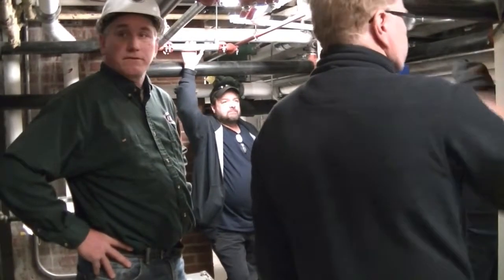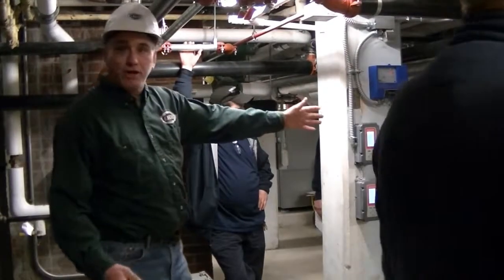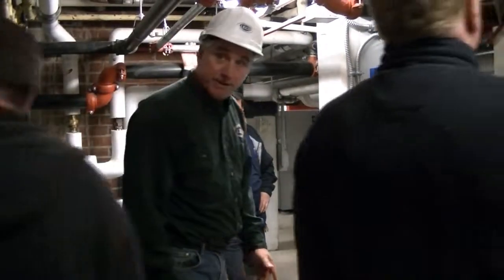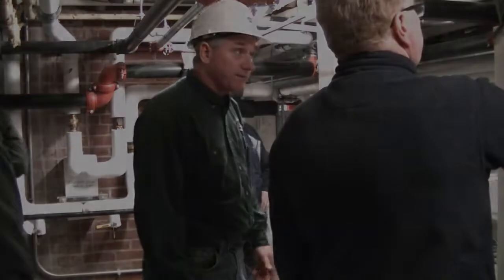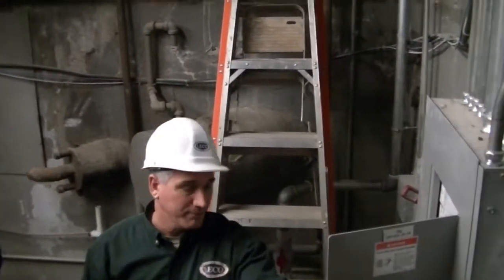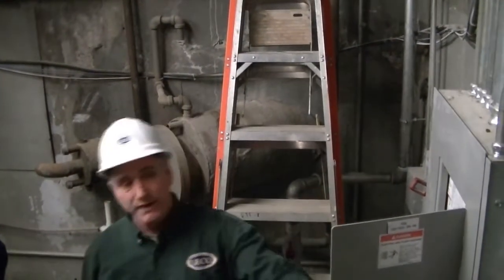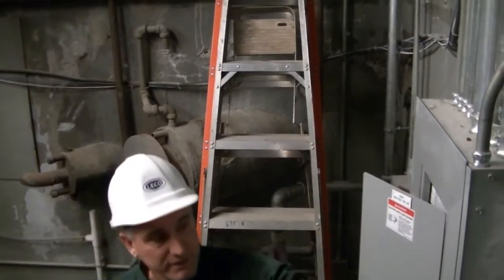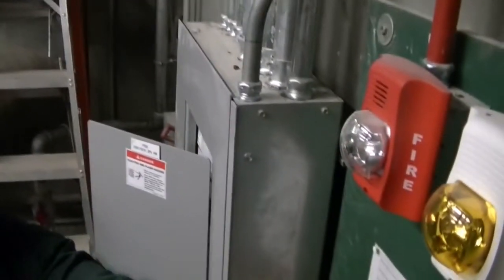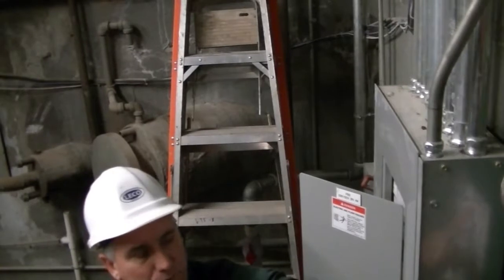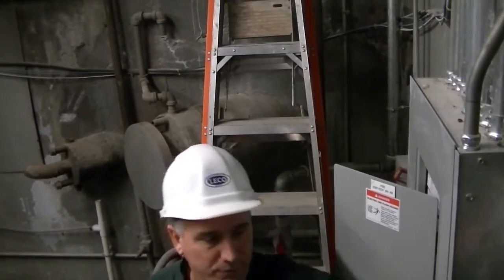Where are the breakers? Breakers are down here in the boiler room. We can take a walk down here. Yeah, the mechanical room, and I can show you the panel. Here's the panel, that gives you the circuit number. There's also a chart here. I also put a little cheat sheet on the wall here, which lists all the equipment, the panel it comes from, where the panel is located, and what circuit number it is.